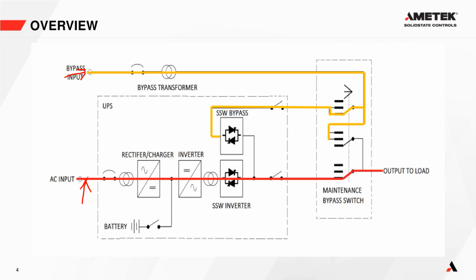Normal power flow is from the grid supply, which is usually a 3-phase 480 volt supply in North America. That goes into our system through a transformer and then into our rectifier charger block. That rectifier charger block charges the batteries at the correct voltage, and then it goes into the inverter, and that DC is then converted back into AC.